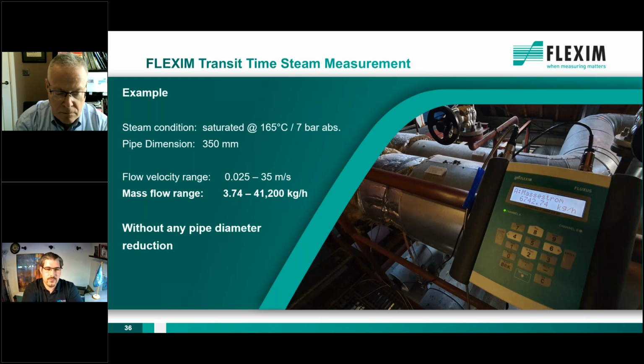And back again to the Würzburg application. Pipe diameter is 350 millimeters. We have saturated steam at 165 degrees C, and we can measure a flow range between 3.74 and 41,000 kilograms per hour, so 41 tons. And this is again without any need of pipe diameter reduction and so on.